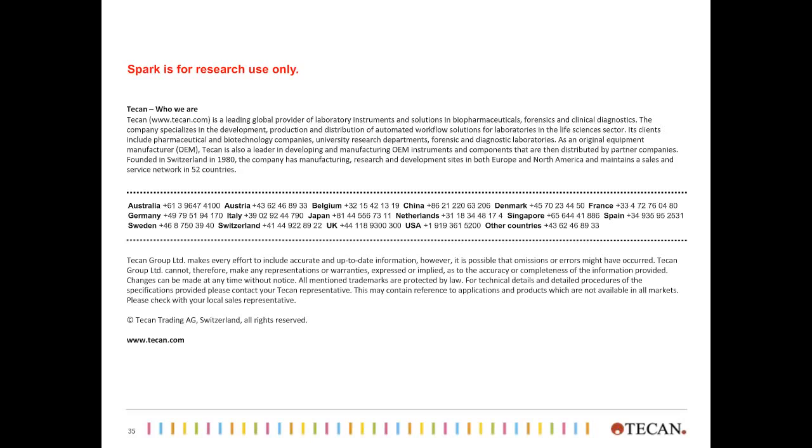Well, I think I'm going to answer this. Primarily it depends on the reader design. The main heat sources are all types of electronic components, the power supply inside the reader, and the light sources, for example the flash lamp or the laser, whatever light source is used in a particular reader. And the longer these components are switched on and running, the more heat will build up inside the reader. So that is the main contributor to instrument warming.